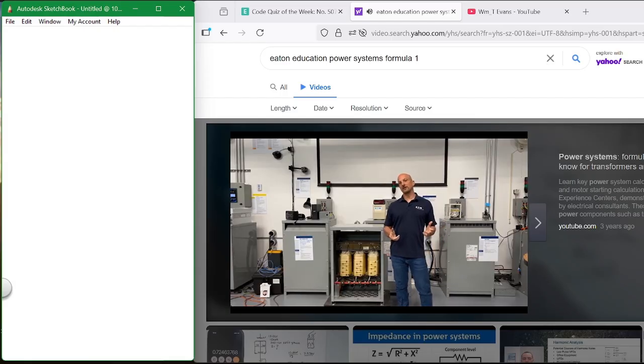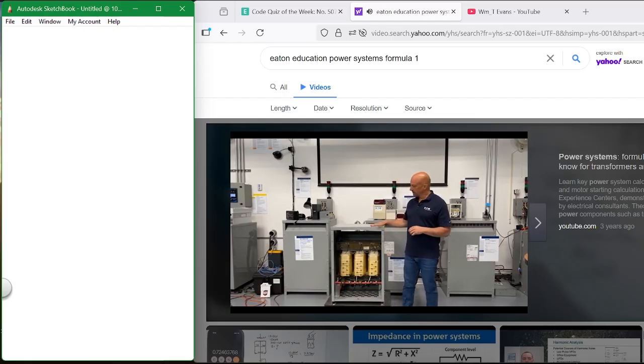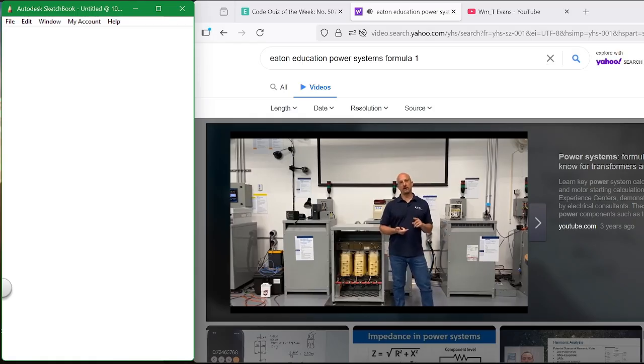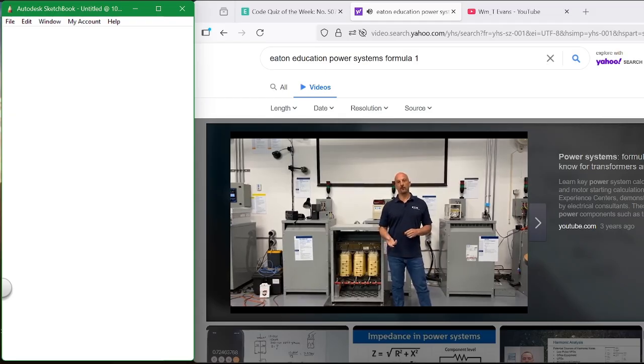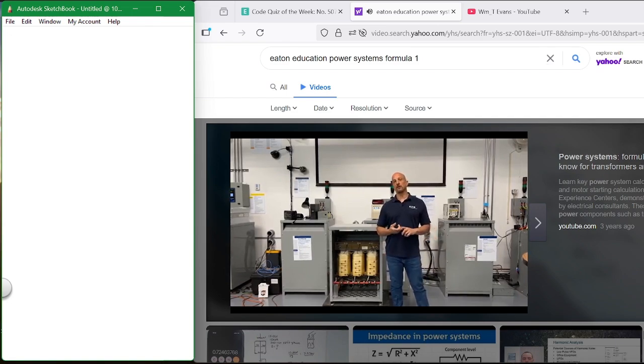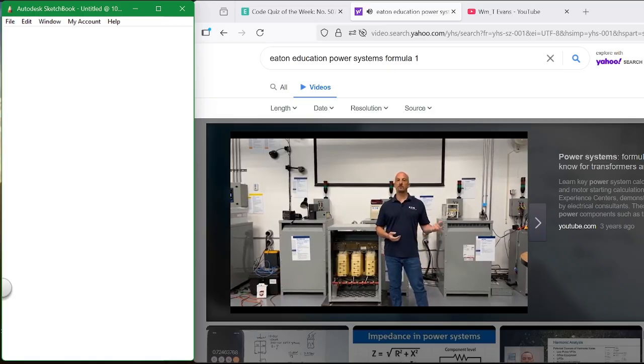So to get to the calculations that we need for a transformer like this, we want to think about full load amps on the primary, full load amps on the secondary, breaker sizing for primary and secondary, and then also fault current on the secondary. How are we going to get that information? Well, we're going to go up to the nameplates of these transformers and find out the information that we're going to need to plug into our equations to calculate those values.